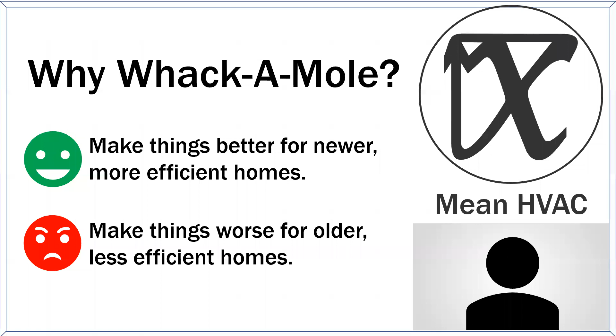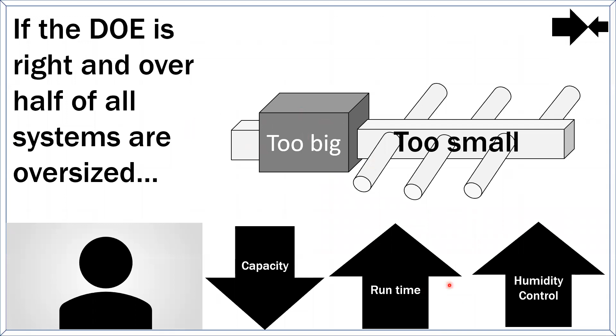This is one of my favorites. If the DOE is right and half of all systems are oversized, that means my air conditioner is too big and my ductwork's too small. And what does that do? It actually balances out and makes it work. Why? Because not enough airflow reduces the capacity of the unit, increases runtime since capacity is lower, and increases humidity control. Less air across the coil means more time in contact with the coil, so I get more moisture removal. The coil gets colder faster because I'm not dumping as much energy into it. It's a win all around, except for efficiency.